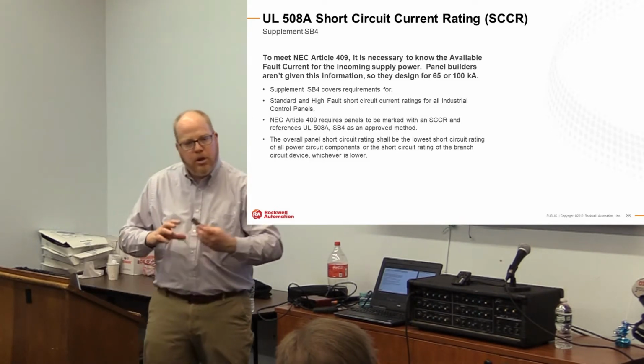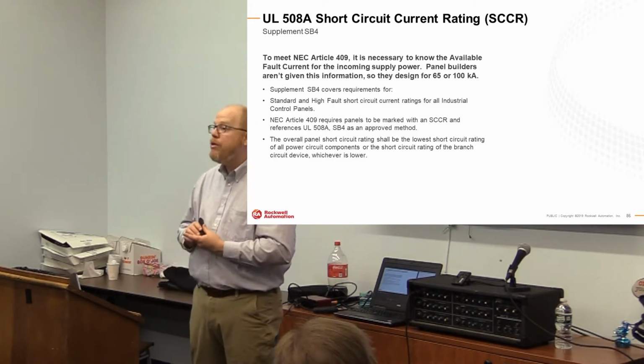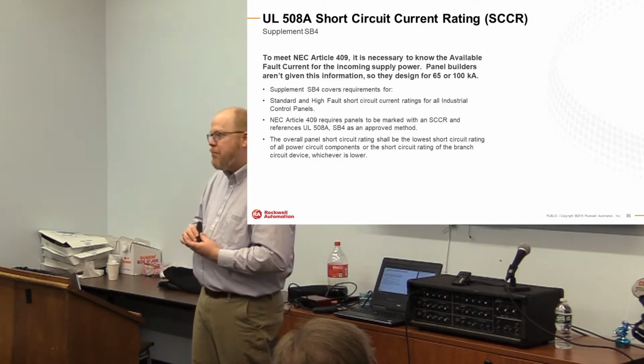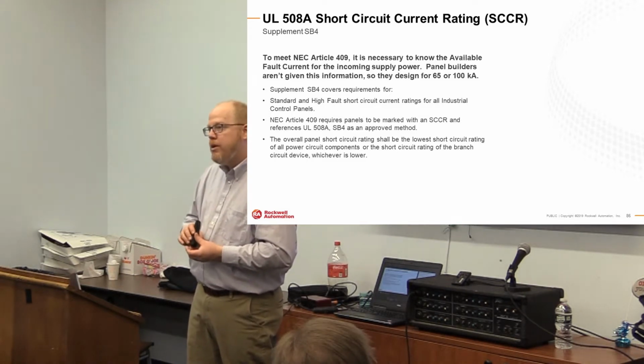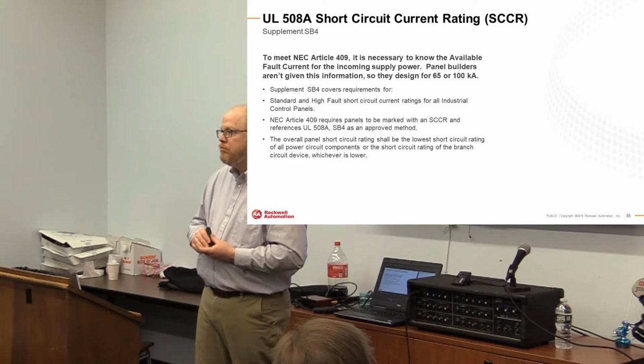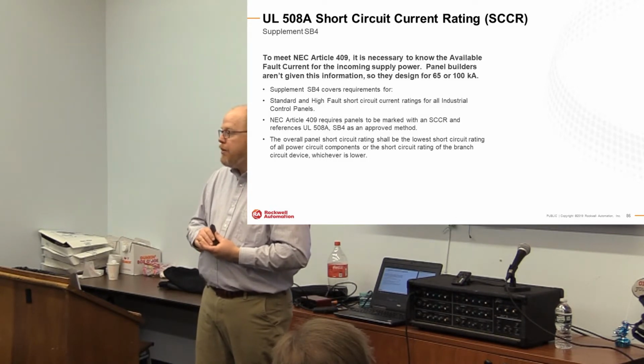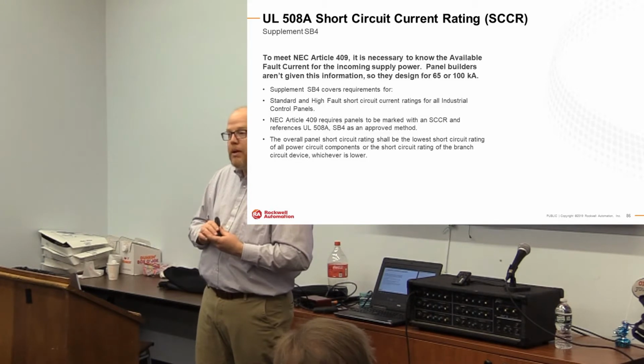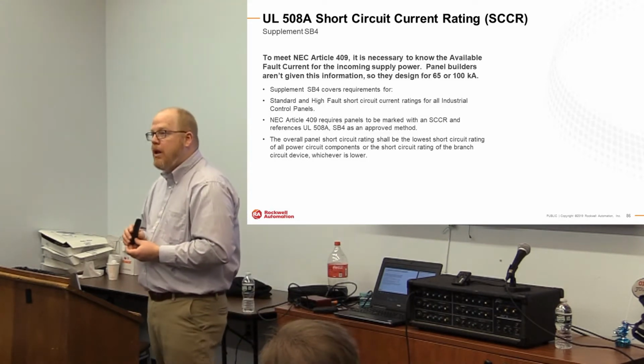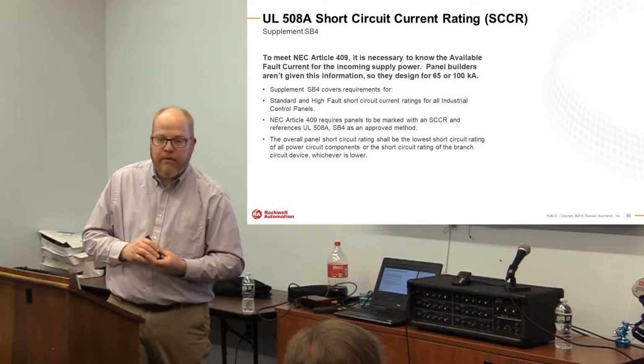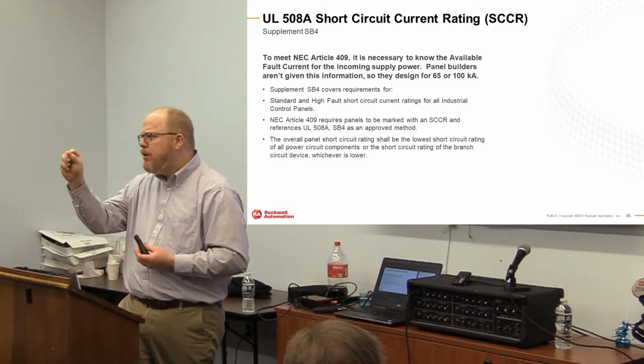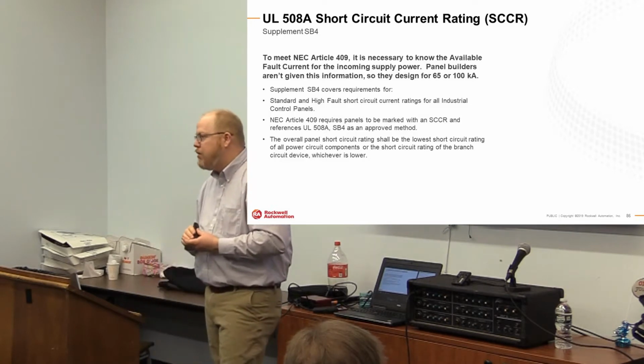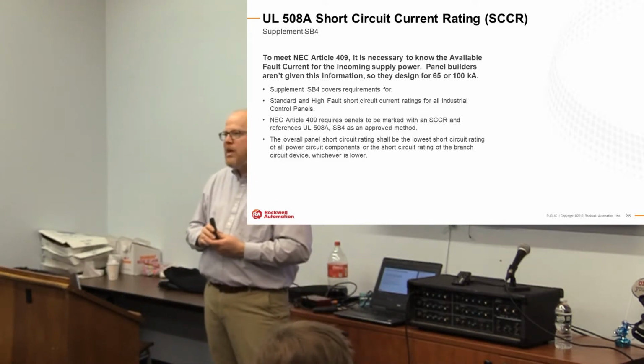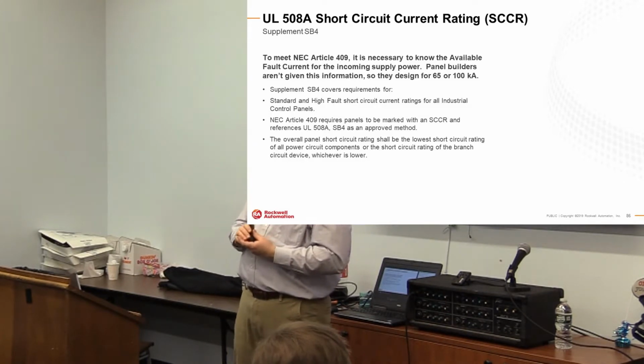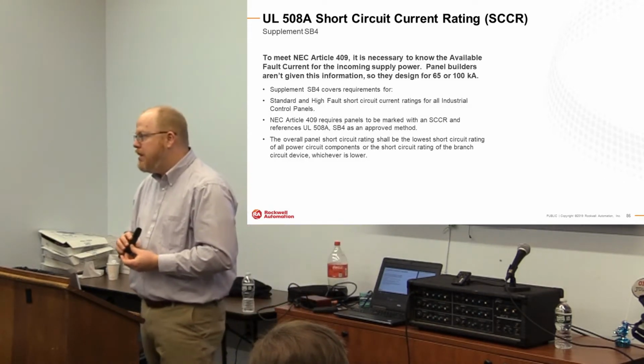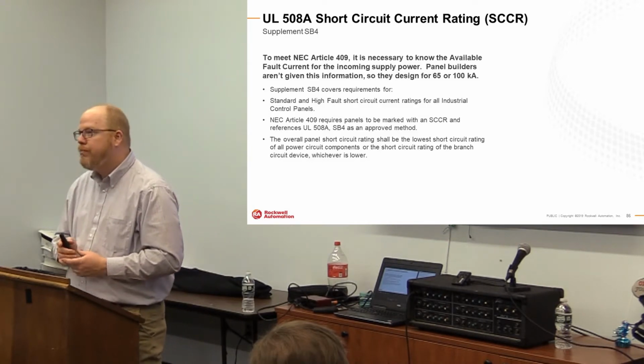It points out that you, as the panel builder, are required to label a panel with a short circuit current rating. It does not prescribe what the rating should be. Where does that come from? Any thoughts? Yeah, from the power evaluation, from your customer, ultimately. They need to know what it's connected to, right? And so sometimes that is not information you're given. And you may even say, but it's on the inquiry form. Yeah, it should be there. No, not always. You're not always given that data. So that's why they'll just say, give me 65, right? They're doing the old peanut butter approach, which is fine and all, but it gets to be sometimes expensive and hard to accomplish.